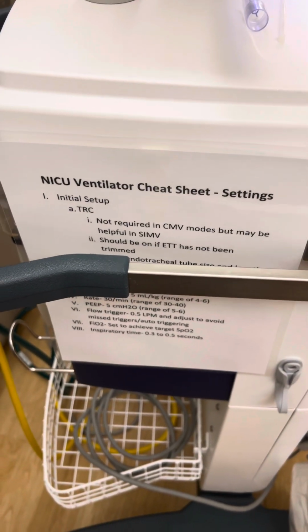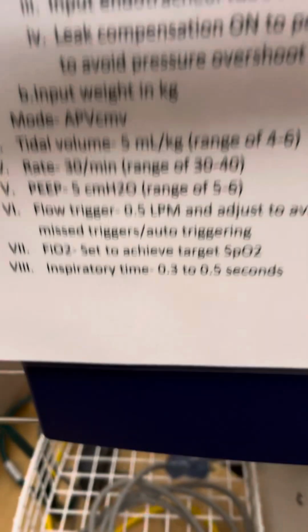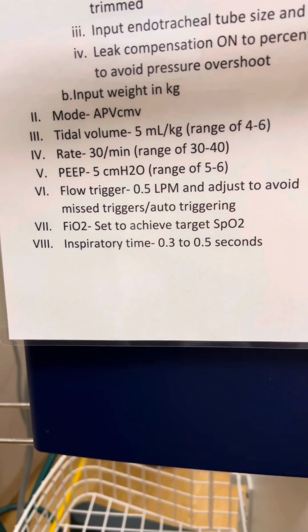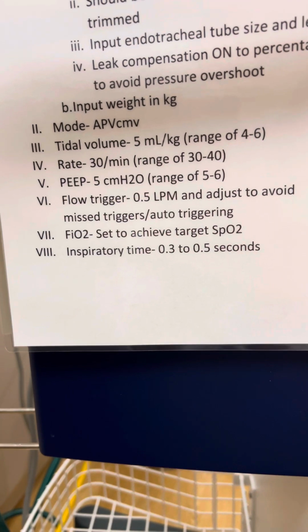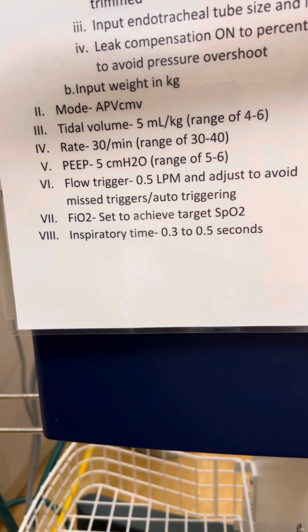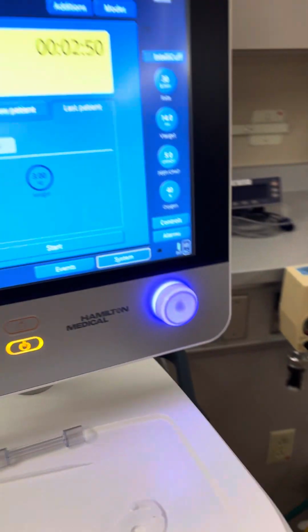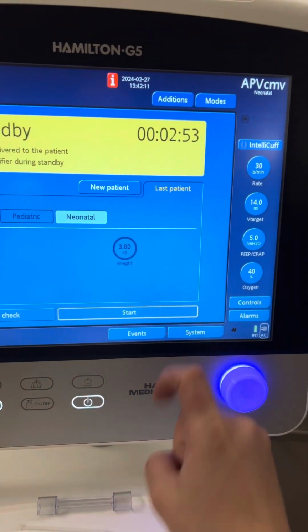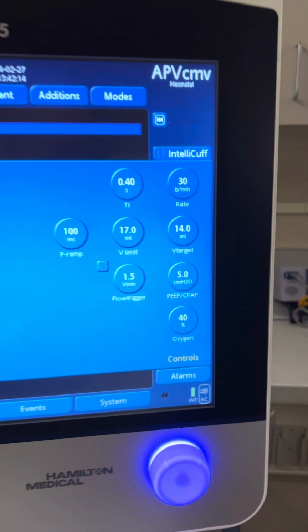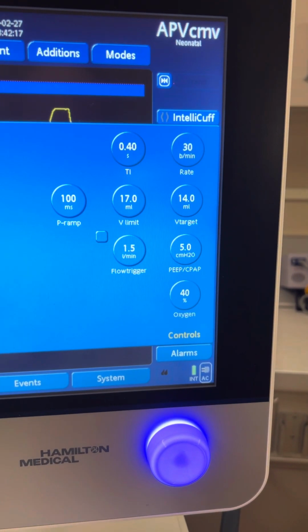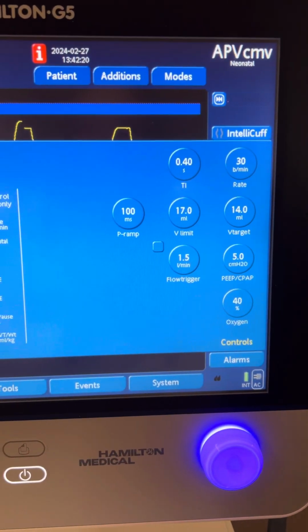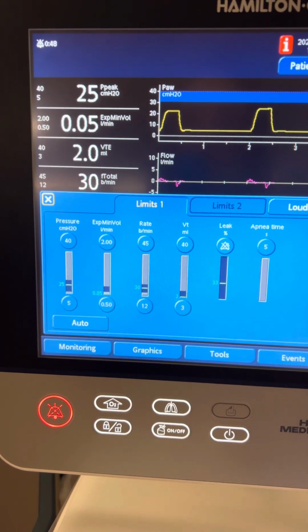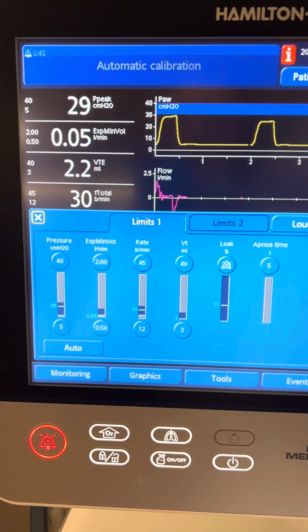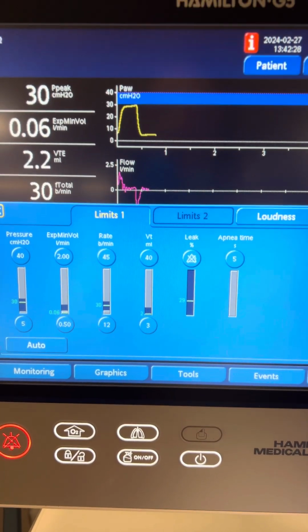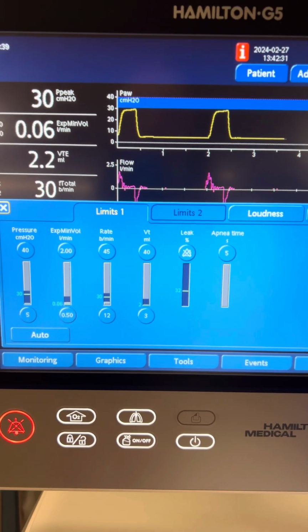One of the things I added here was this ventilator cheat sheet. Dr. Grebe, the medical director, just asked that we switch to using more APV-CMV versus SIMV pressure control. And then there's your target ranges there. One of the things the neonatologist just mentioned to me, if you do start them in this mode, we do have the volume limit, which you would want to verify with them, but we don't have the target limit under controls. I did tell her it's controlled by our alarms. It's 10 below whatever our pressure setting is. So that's something that we would just need to verify with our provider as well, is what we want that pressure limit to be since we're now in a volume targeted mode.